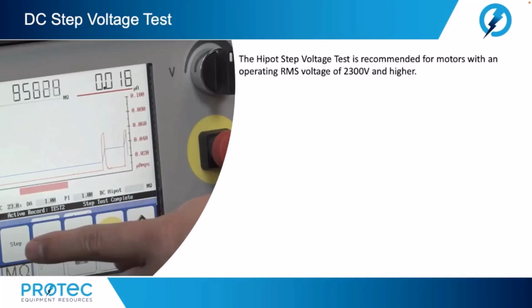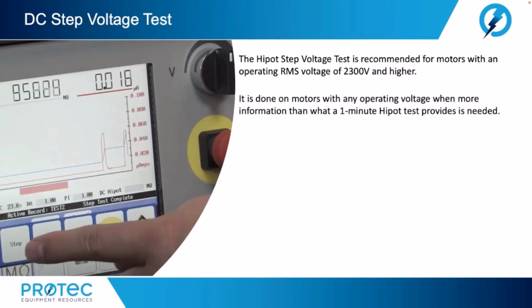The next high potential test we're going to look at is the DC step voltage test. The high pot step voltage test is recommended for motors with an operating RMS voltage of 2300 volts and higher. It is done on any motors with any operating voltage when more information than a 1-minute high pot test provides is needed.